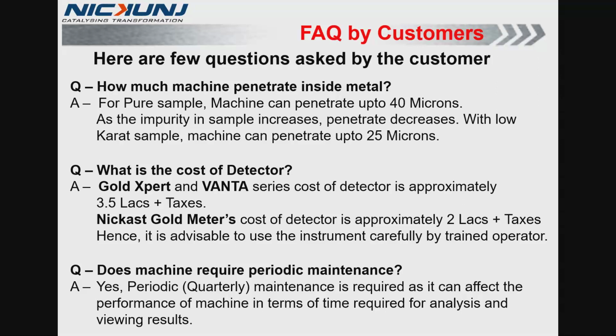How much does the machine penetrate inside metal? For pure sample, machine can penetrate up to 40 microns. As the impurity in sample increases, penetration decreases. With low carat sample, machine can penetrate up to 25 microns.